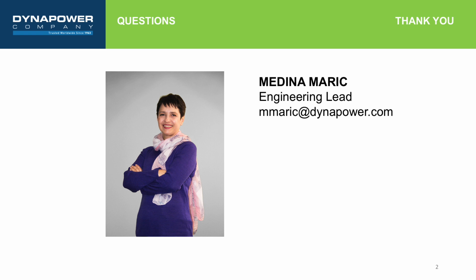Typically not. VAR compensation from drives is a very unusual feature, and the drive would have to be specially ordered so that it would be able to supply VAR support. Drives, depending on if they're 6-pulse or 12-pulse and whether they're 100 horsepower or 1,000 horsepower, of course, are built very differently. We typically do not manufacture drives, but we understand the technology. It's very unusual to provide VAR support. In a different product built on a similar platform, an inverter product, also done in high-frequency topology, we do supply VAR support, but not in the power supply world, and certainly we have not seen it in the drive space.